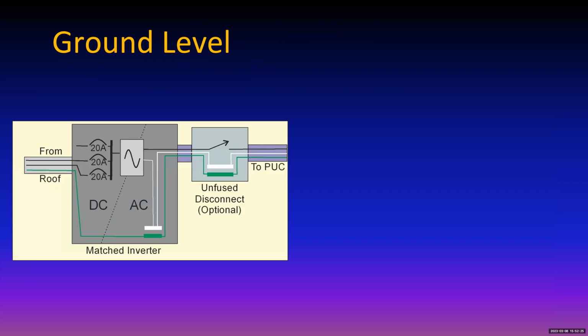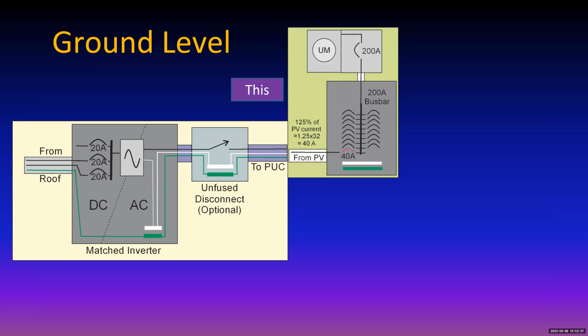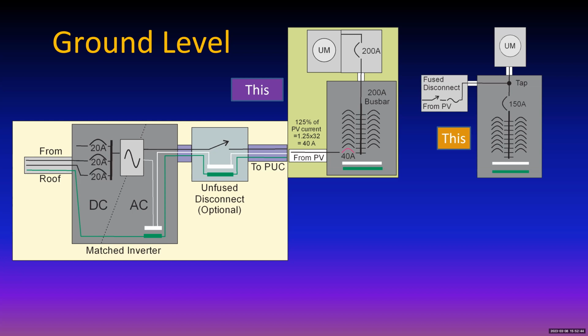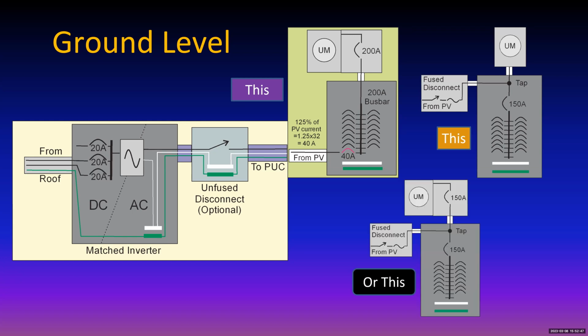And so what's at the ground? Well, this looks familiar. You've got an inverter that matches the stuff on the roof, a disconnect, and you might connect it up like that. Or that looks familiar, doesn't it? The old familiar backfed circuit breaker, or you might try one of these, a line side tap, or maybe one of these, a load side tap. One way or another, you're going to get that thing tied in, as long as your PV doesn't generate more current than your utility feeders are rated at.